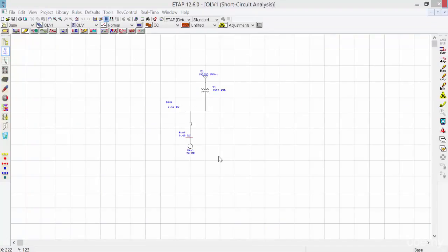And last but not least, using short circuit analysis in ETAP, you can simply put a fault anywhere in your power system and ETAP automatically shows you the next trip device that would trip and also the information about the arc flash. Just click on Run ArcFlash Fault Insertion Calculation. You will see the arc flash sign at the cursor of your mouse. The color of this arc flash sign is black, and as soon as you hover it over the bus that you wish to fault, it turns yellow.